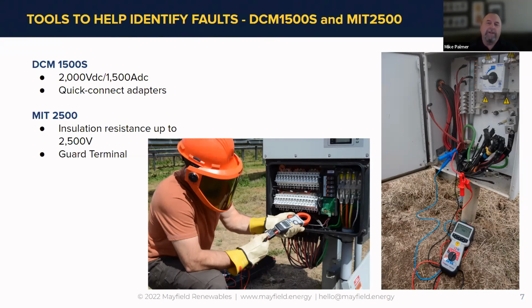But on the module side, I think there is a caution, and there are people on this call who have been testing through the module for years. There's no surprise there. Of course, Ryan and I have never done that. But I think for the most part, caution is best. The cable itself is straightforward: do it up to the voltage limit of the array. And when the module is tied in, err on the side of caution to get approval, so if something happens in 2 months, you're covered.